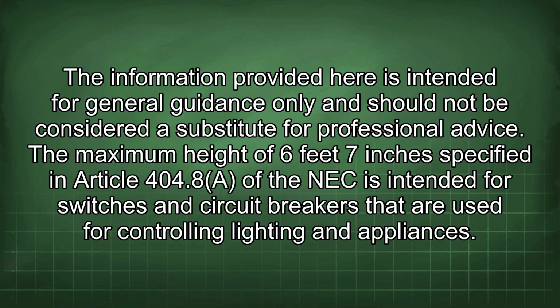The maximum height of 6 feet 7 inches specified in Article 404.8 of the NEC is intended for switches and circuit breakers used for controlling lighting and appliances.